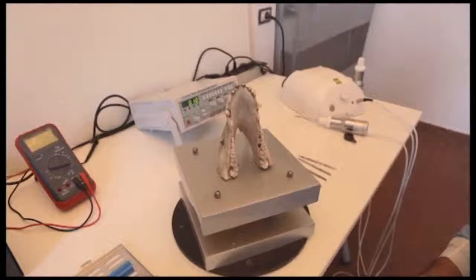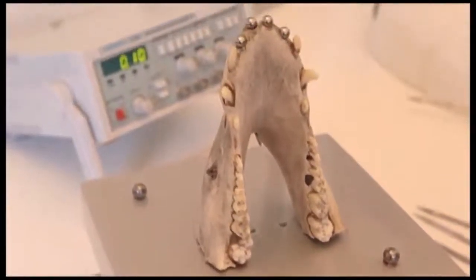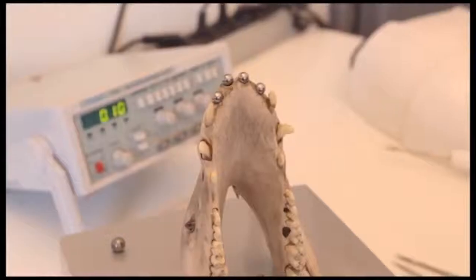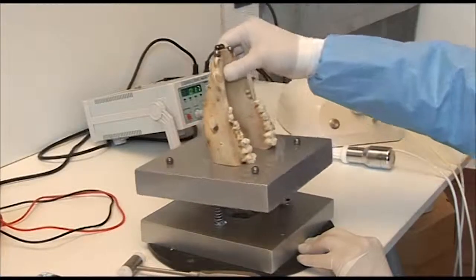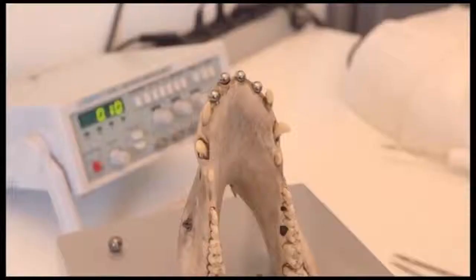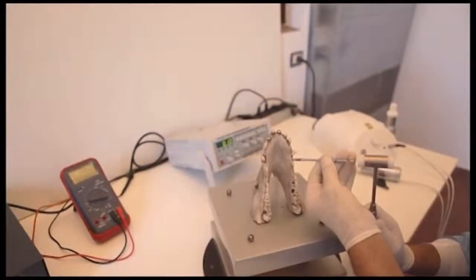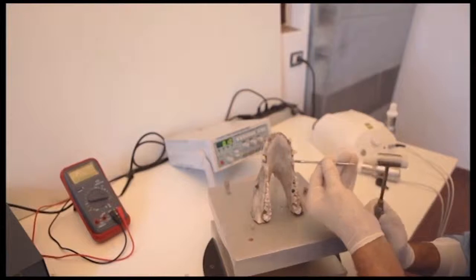Now, the advantages of Magnetic Mallet compared to the manual hammer in the osteotome practice. We used a simulator representing the craniofacial mask with its jaw and some spheres simulating the inner ear otoliths. The bottom structure springs react like the neck of the patient. The hammer is handled by the right hand, and consequently, the osteotome must be held by the left one, provoking a certain difficulty positioning the osteotome in the site.